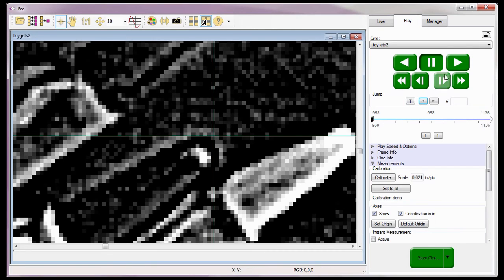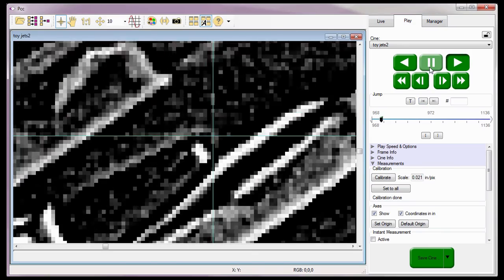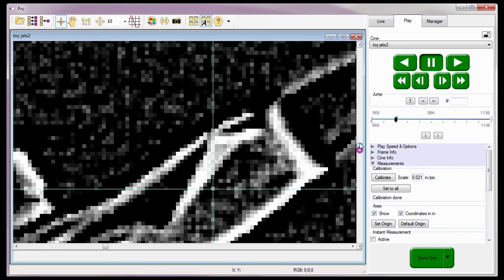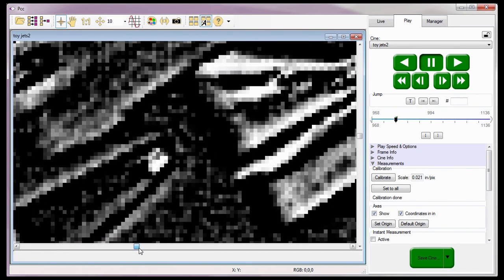Now let's advance the CINE a few frames and relocate the tip of the jet. I'll use the preview panel sliders to locate the tip of the first jet, then move the cursor so the center of it is on the tip of the jet. The software calculates the XY coordinates and reports them in the status bar just like before. I could have measured coordinates for multiple points on the image if desired, but this demonstrates how to perform coordinate measurements. That's how easy it is to do coordinate measurements with the PCC software.